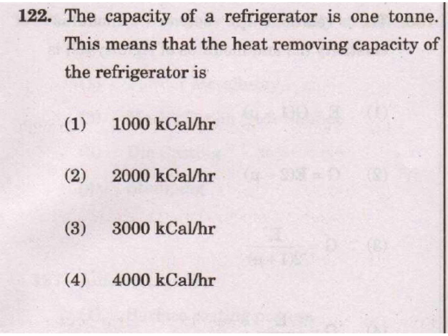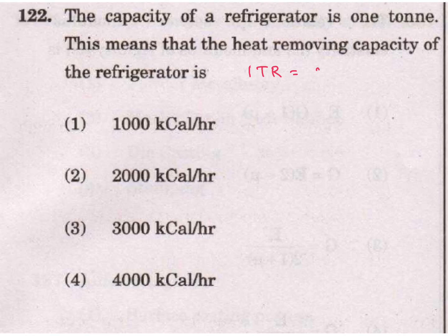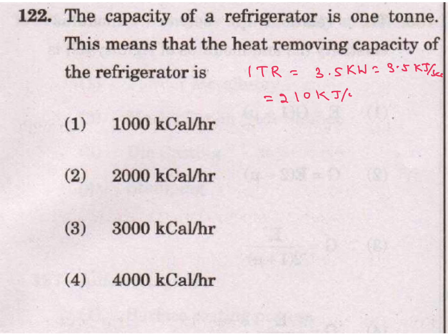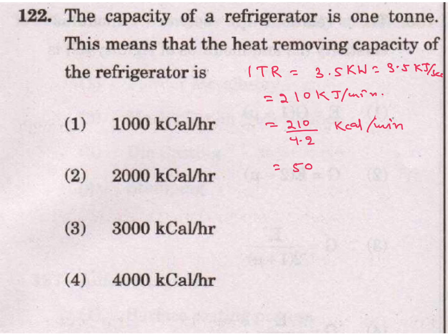The capacity of a refrigerator is 1 ton. This means the heat removing capacity of the refrigerator is measured in kcal per hour. 1 ton of refrigeration equals 3.5 kW or 3.5 kJ per second, which is the same as 210 kJ per minute. Dividing by 4.2, it comes to 50 kcal per minute.